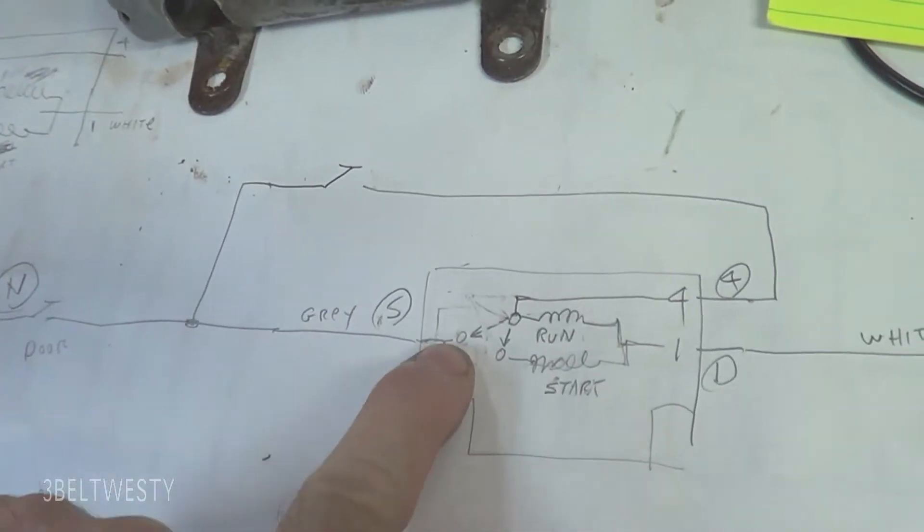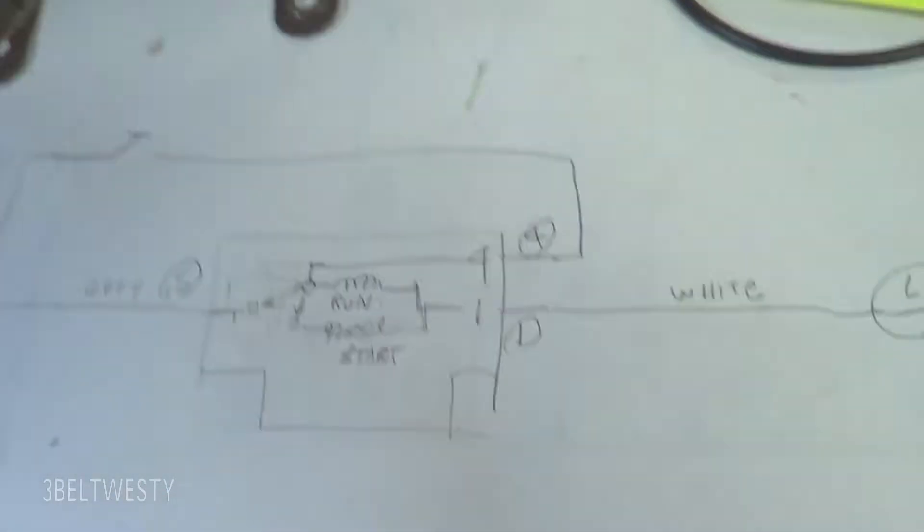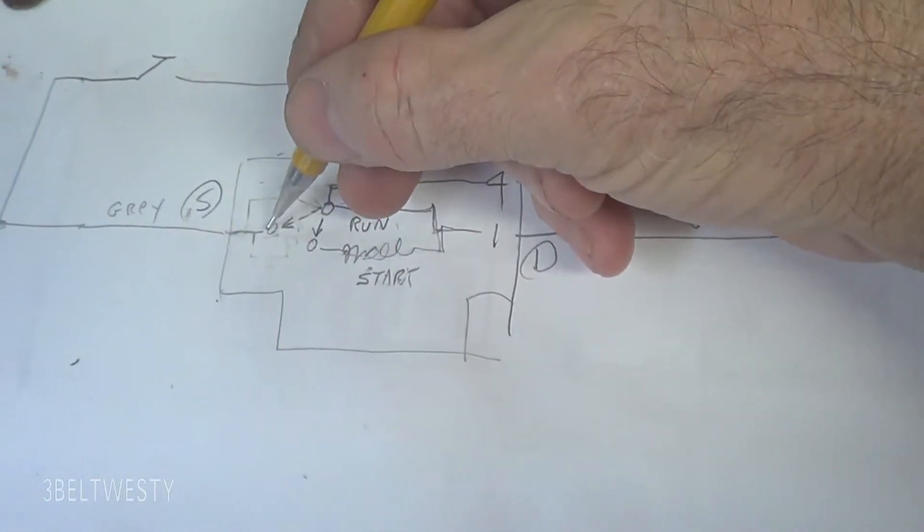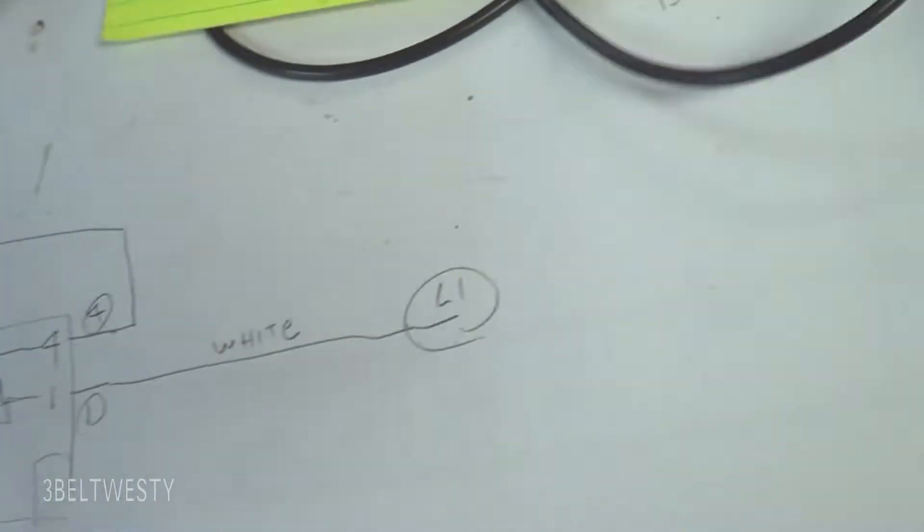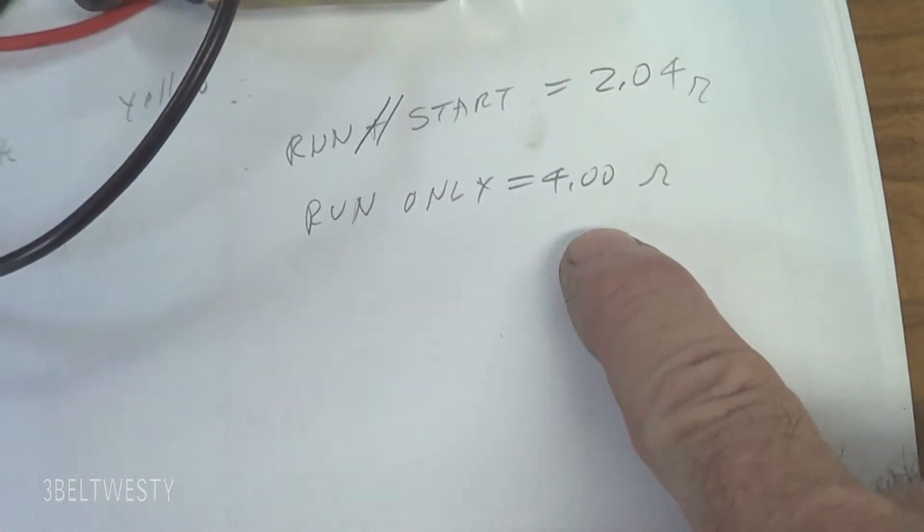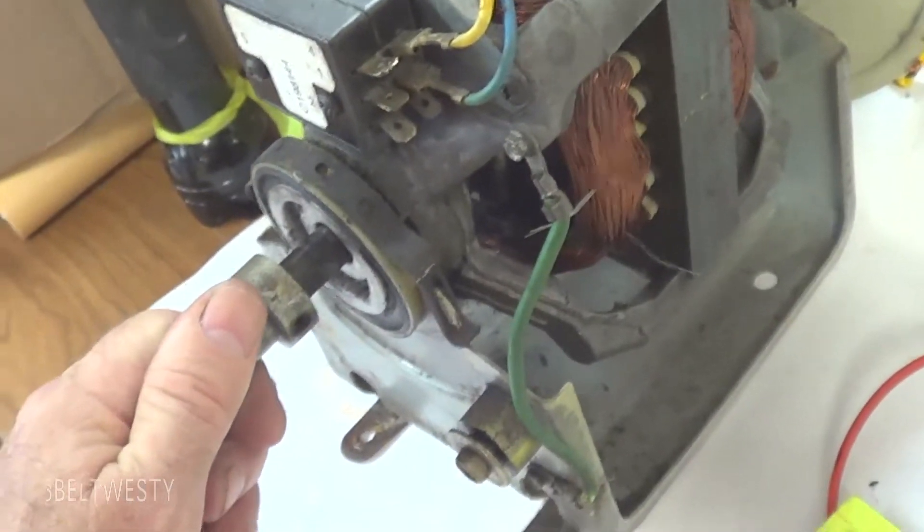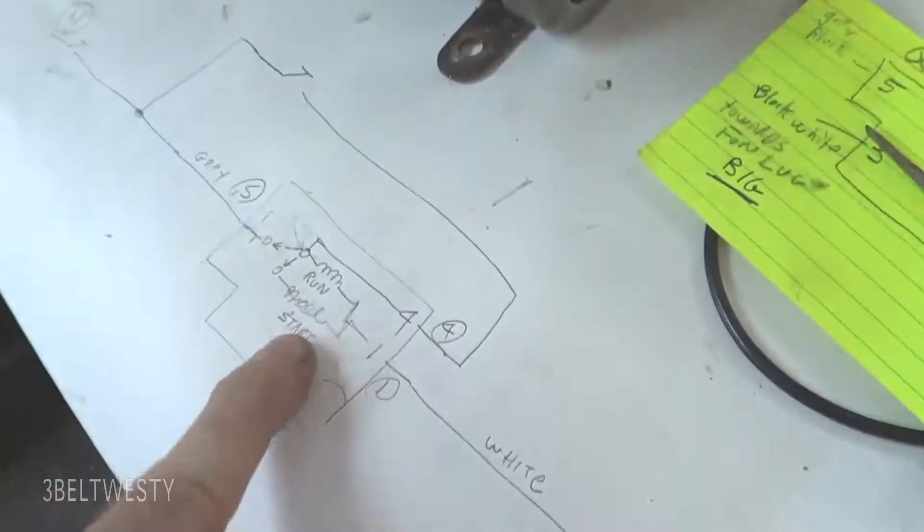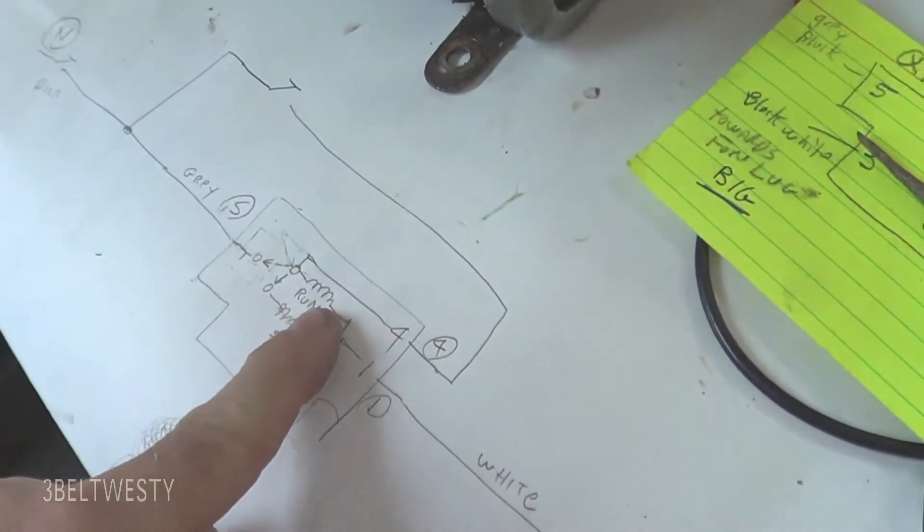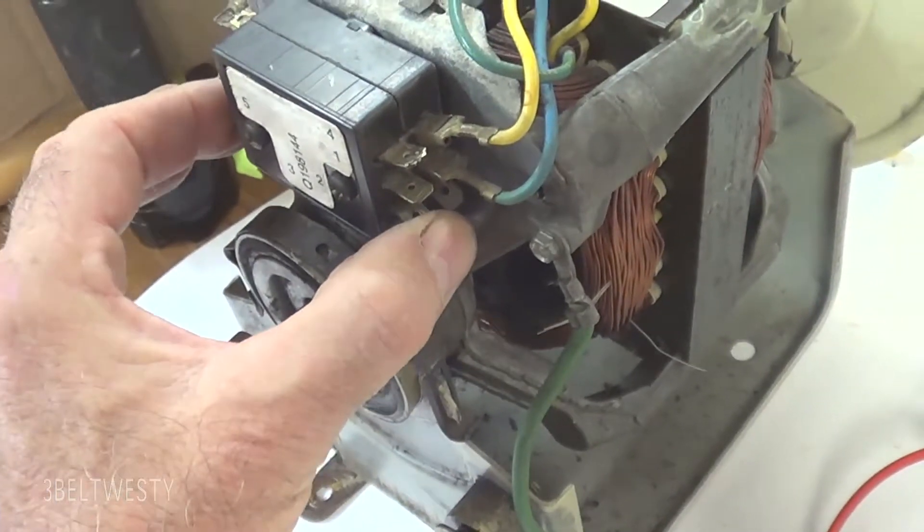So, this current, this terminal here, this one isn't hooked to anything until it comes up to speed. So, when it goes up to speed, this flies over and takes out the start winding. And what I've found out here is the run and start together is about two ohms. Run only is about four. So, there's two things are going on. When this comes up to speed, it takes out the start winding. And then over here, it goes ahead, and it's only using the run winding. And then it also goes through and connects this up so the heater element can work.